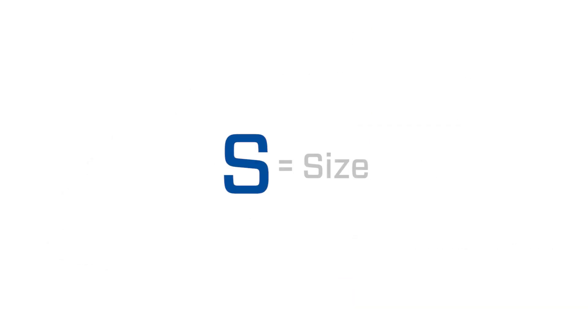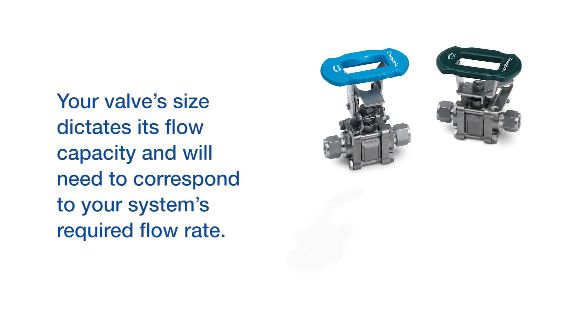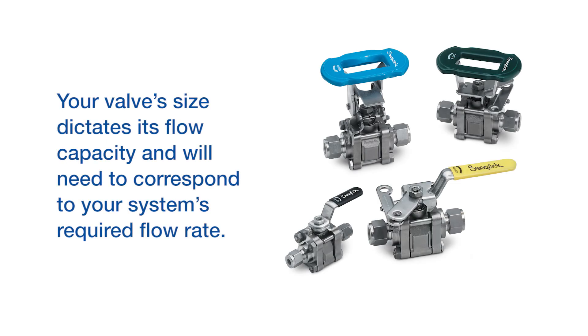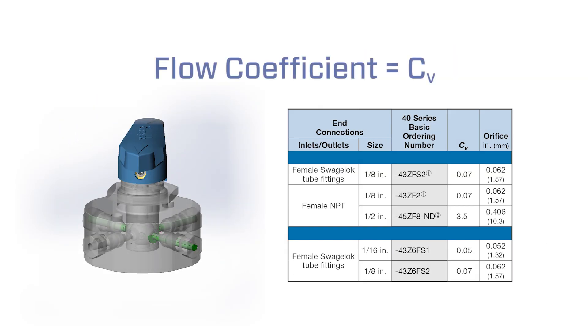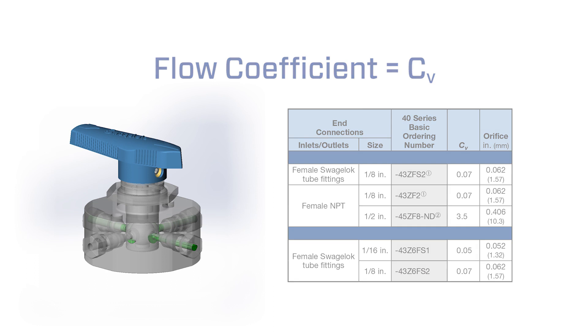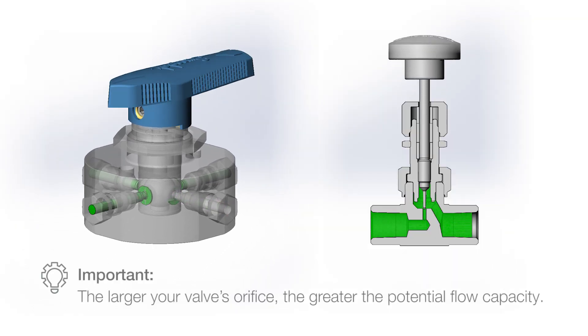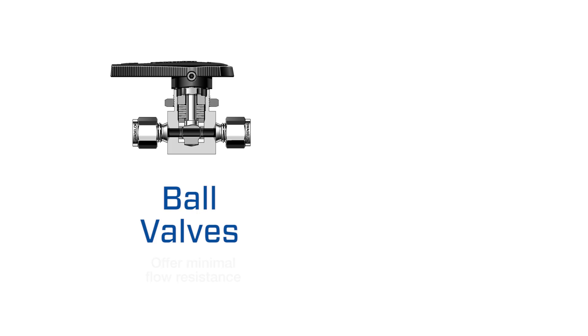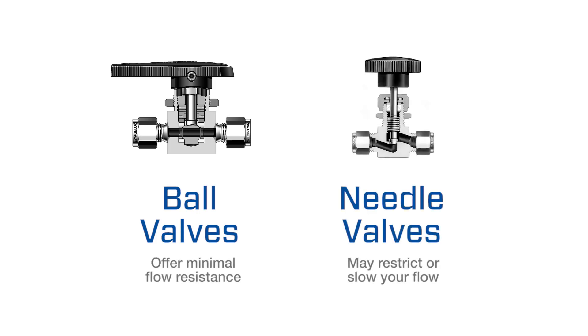First, determine the size you need. Your valve's size dictates its flow capacity and will need to correspond to your system's required flow rate. Manufacturers typically provide a flow coefficient indicating the relationship between pressure drop across the valve and the corresponding flow rate. The larger your valve's orifice, the greater the potential flow capacity. For example, ball valves offer minimal flow resistance, but a needle valve may restrict or slow your flow.